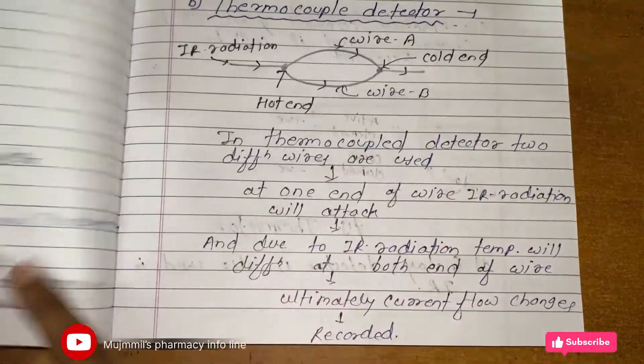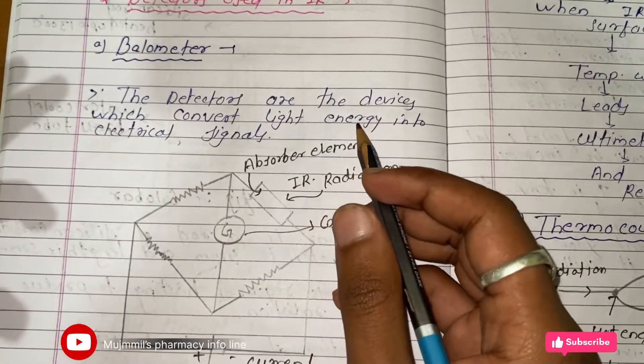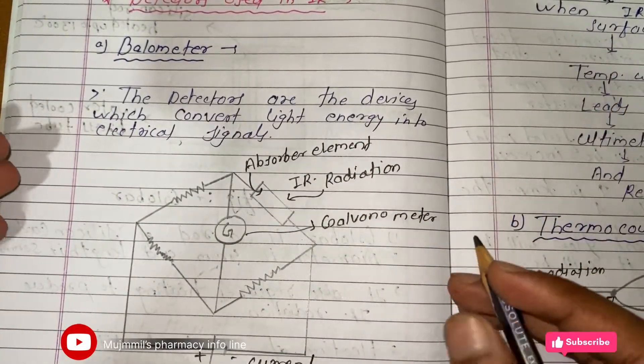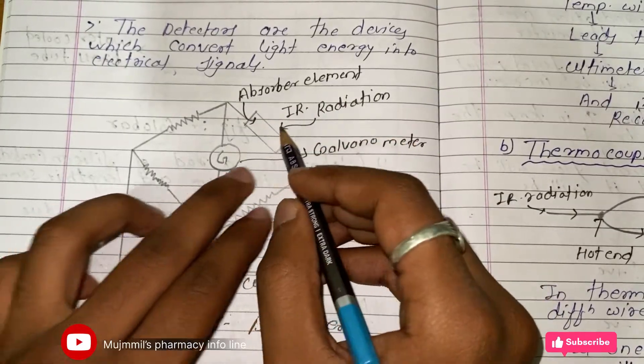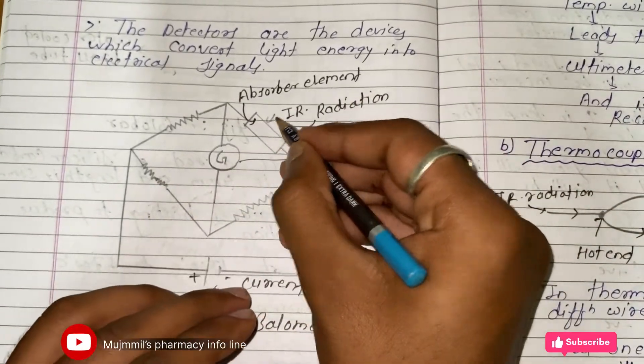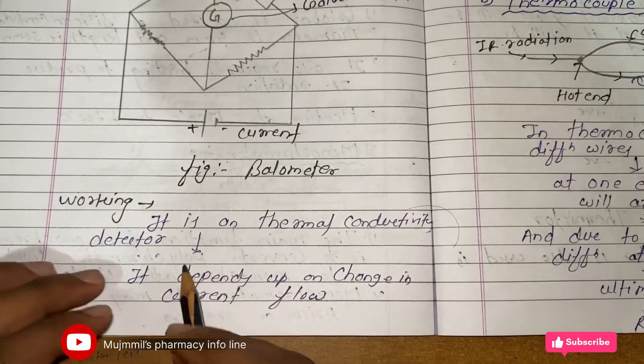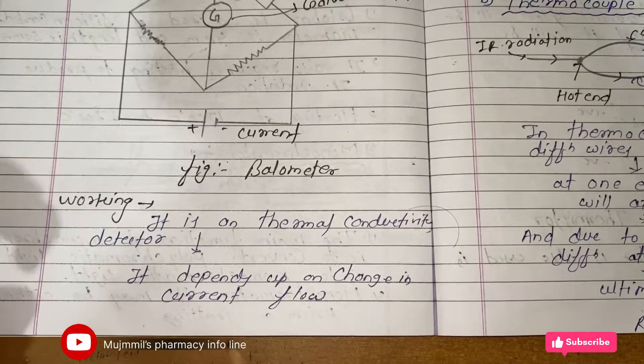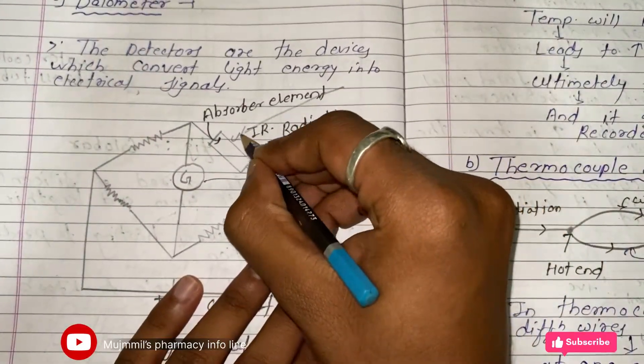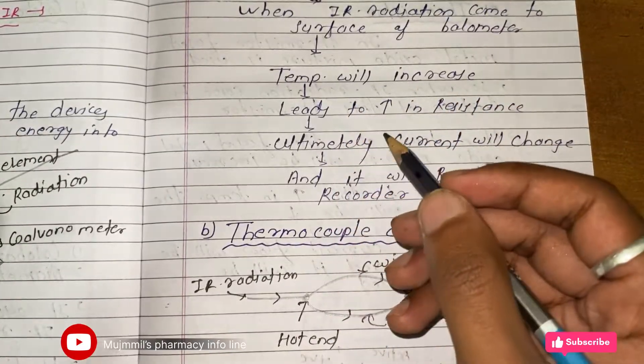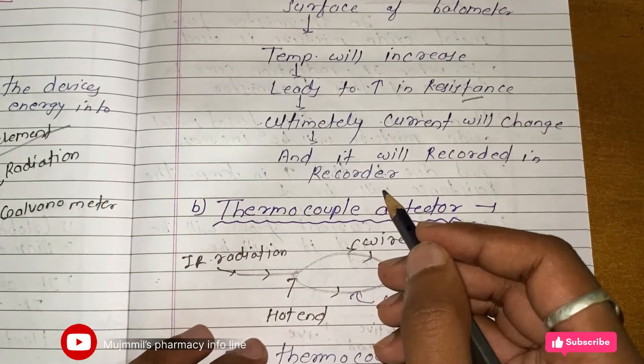Let's see the detectors used in IR spectroscopy. Detectors are devices that convert light energy into electrical signals. The first detector is the bolometer. It uses a galvanometer and has an absorber element where IR radiation is incident. The bolometer is a thermal conductivity detector dependent on change in current flow. When IR radiation hits the surface, it increases temperature, which increases resistance, and ultimately the current changes and is recorded.